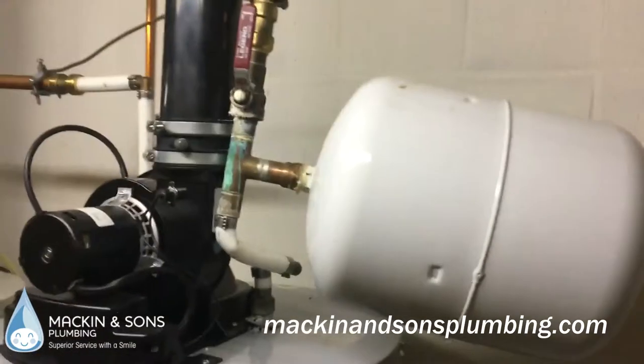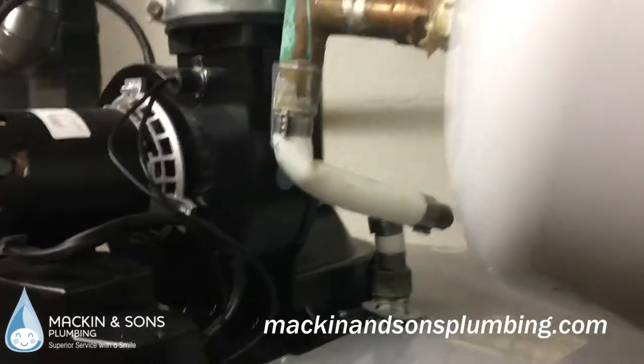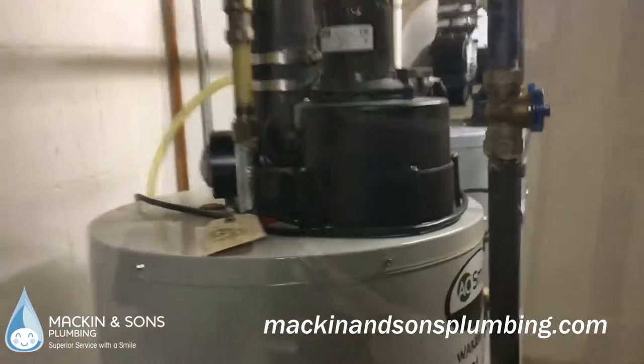If you notice, it's totally crooked and it's a miracle that this pipe just didn't break and flood their basement. There's also plastic water lines coming off the top of the heater, which is illegal, and the vent line is crooked. I don't know who put this in, but they obviously weren't a plumber. We're going to get this fixed up and show you the finished product when we're done.